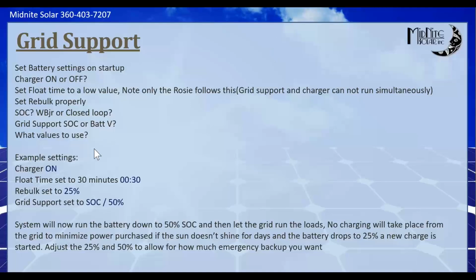And then what values do we want to use? How deep do we want to dig into the battery? Again, this is totally up to you. If your goal is to minimize grid usage, and you're like me where you have way more PV available during the day than you can use on loads, if I started the morning with a battery at 90 to 95% full, my controllers would be in float and regulating by about 10 a.m., and I'd be throwing power away.